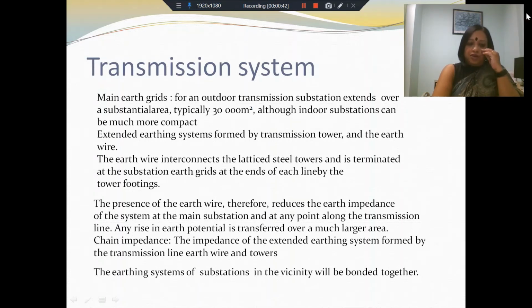But apart from the main earth grid, which encompasses the entire outdoor area, in the case of an outdoor transmission line, there are already certain aspects which are part of the earth system. You have the transmission towers which are earthed. You have the earth wire or the ground wire over the transmission line, which has the principal function of protecting the phase conductors from lightning strike, but at the same time, they're also earthed. So the earth wire interconnects the lattice steel towers and is terminated at the substation earth grid. So you now have an extended earth connectivity, which is comprised of the main earth grid at the earth level, and then you have the transmission towers, and then you also have the earth wire over the conductors.